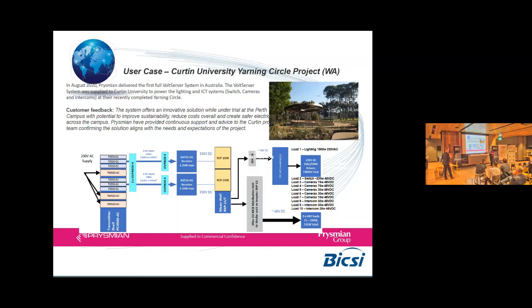The lighting system runs off AC, not DC. So we had to convert the DC power that the VoltServer system delivered back to AC so it could run the lighting system. But then we also had all of the items that ran off the DC system, so we had about nine 48 volt loads going out to the yarning circle to run the PoE switch.